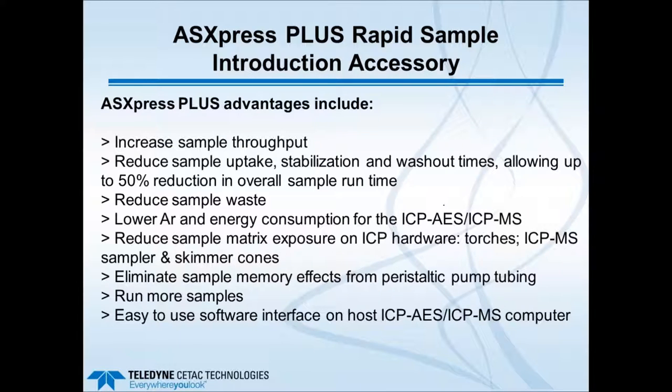Advantages of the ASXpress Plus include: increased sample throughput by rapidly loading fixed-volume loops and injecting quickly into the nebulizer; up to 50% or more reduction in overall sample run time; reduced sample waste and lower argon and energy consumption; reduced exposure on ICP hardware such as torches and ICP-MS sampler and skimmer cones; elimination of sample memory effects from PVC peristaltic pump tubing, since only clean carrier liquid contacts the tubing; the ability to run more samples in the same allotted time; and a relatively easy-to-use software interface on the host ICP computer.